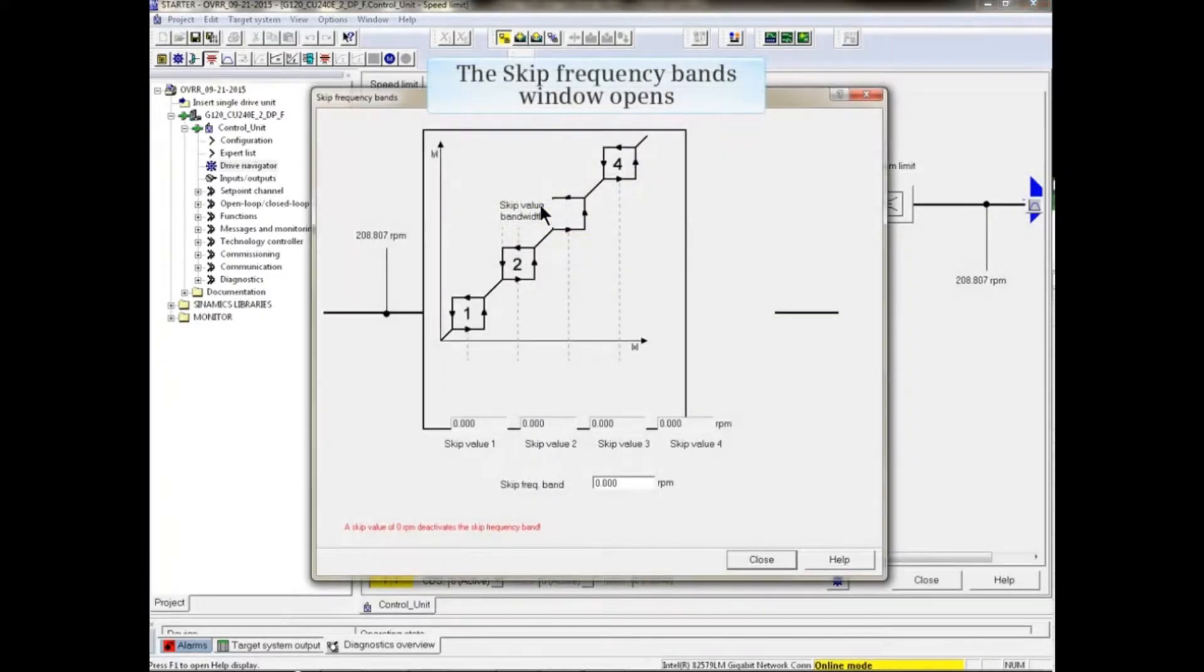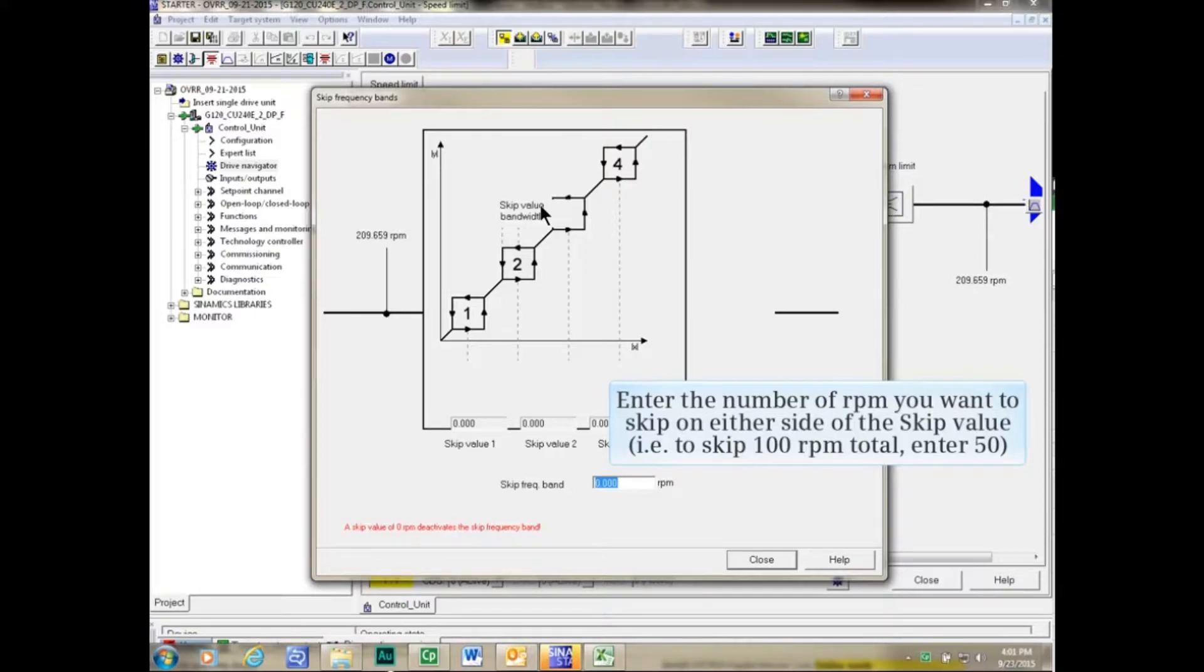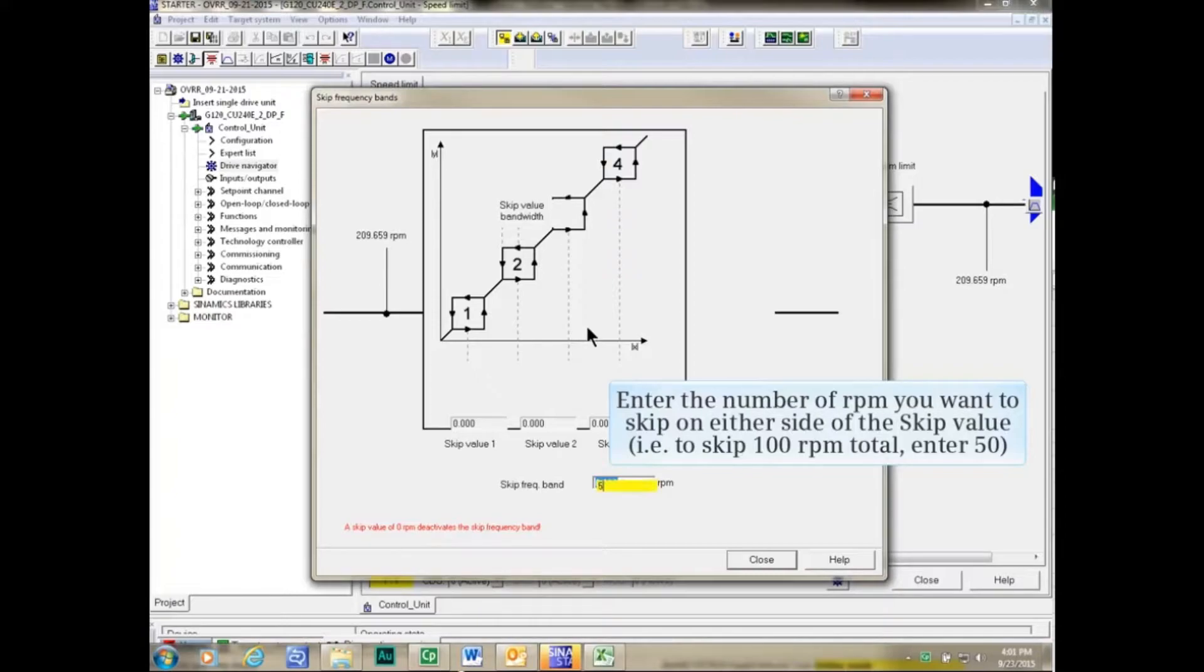The Skip Frequency Bands window opens. Enter the number of RPM you want to skip on either side of the skip value. In other words, to skip 100 RPM total, enter 50 in the Skip Frequency Band input box.